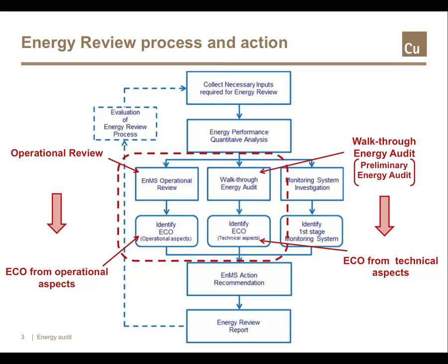A walkthrough energy audit is a preliminary energy conservation analysis following 1 or 2 day site inspections and a survey to identify ECOs. The site inspection is based on visual verifications, studies of installed equipment and operating data, as well as detailed analysis of recorded energy consumption for the defined period of time. Walkthrough energy audits are sometimes called preliminary energy audits.